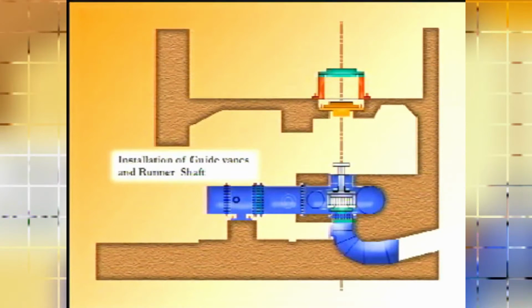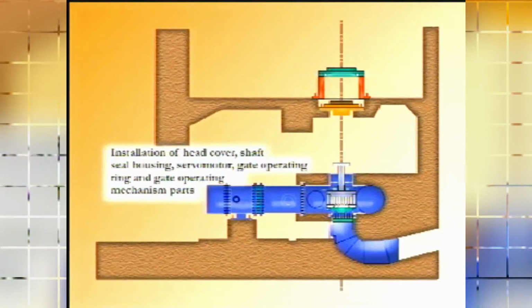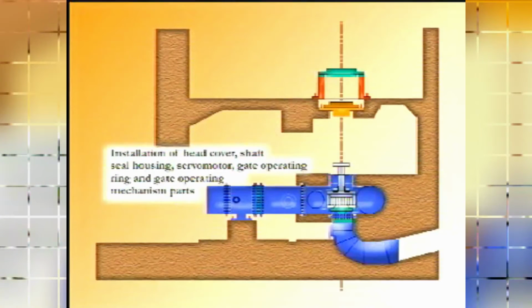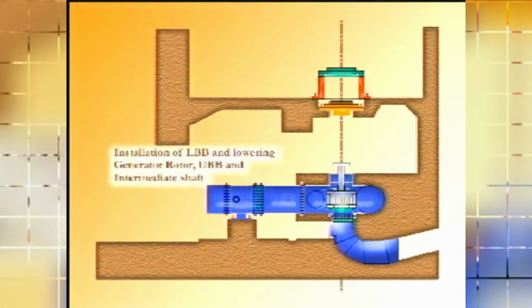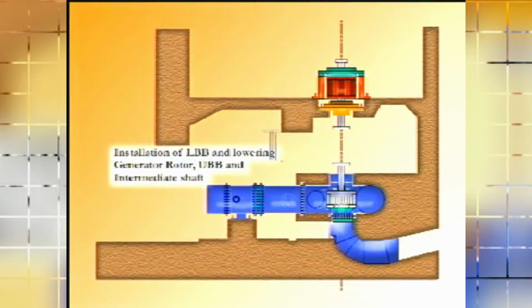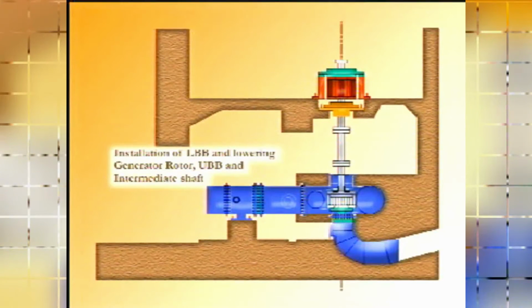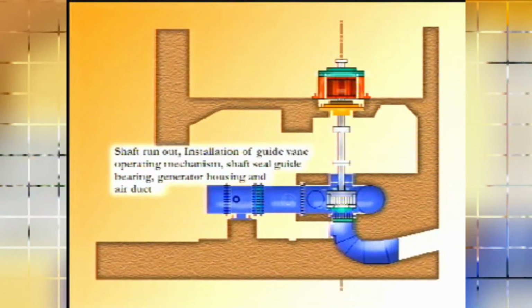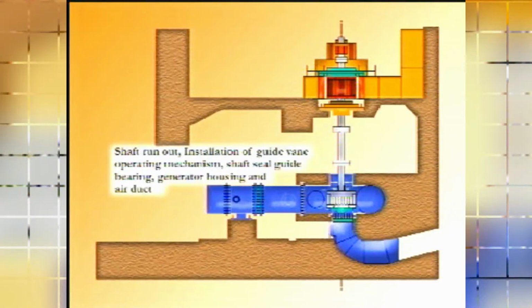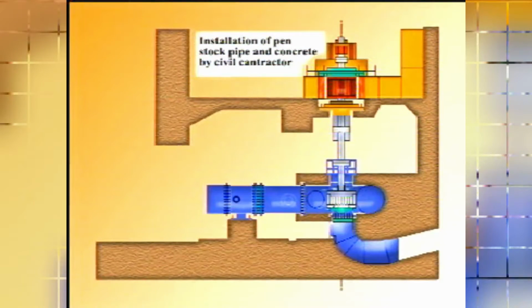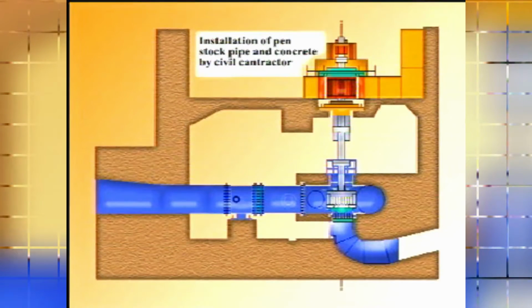Installation of guide vanes and runner shaft. Installation of head cover, shaft seal housing, bearing housing, servo motor, gate operating ring, and gate operating mechanism parts. Installation of lower bearing bracket and lowering generator rotor, upper bearing bracket and intermediate shaft. Shaft run out, installation of guide vane operating mechanism, shaft seal guide bearing, generator housing and air duct. Installation of penstock pipe and concrete by civil contractor.